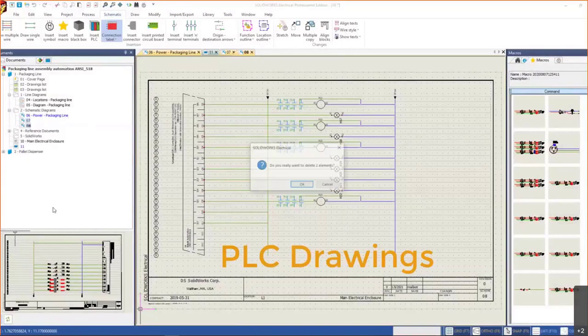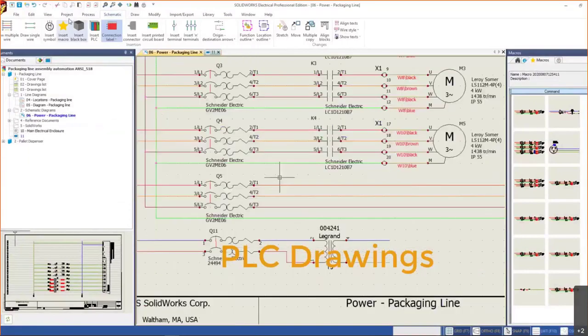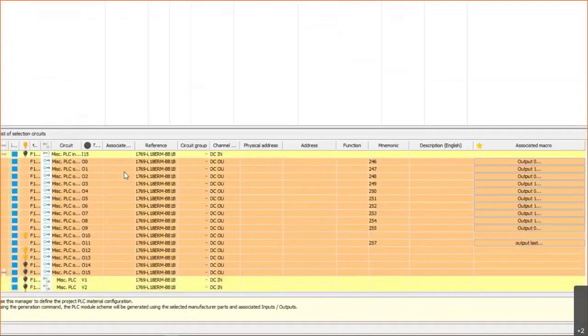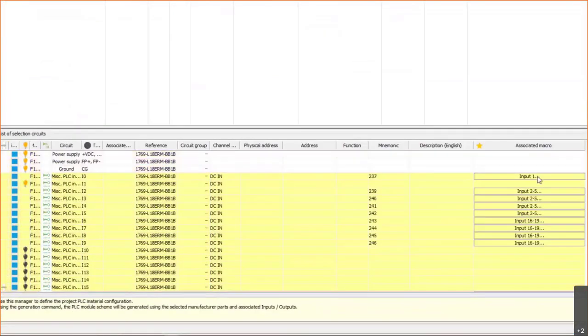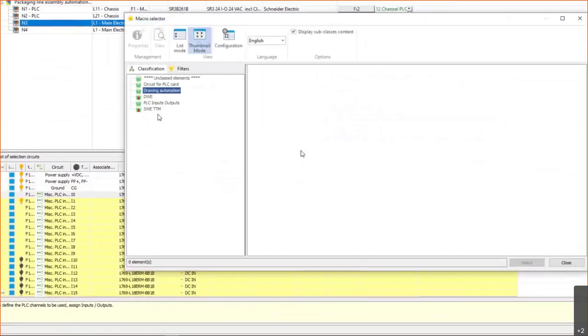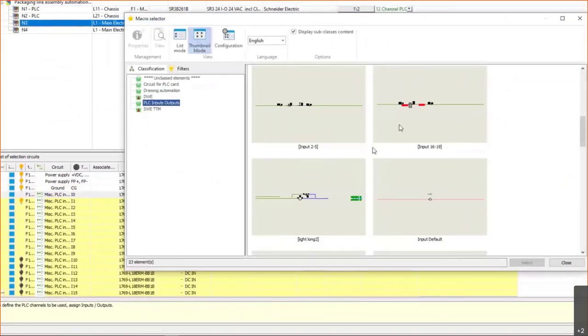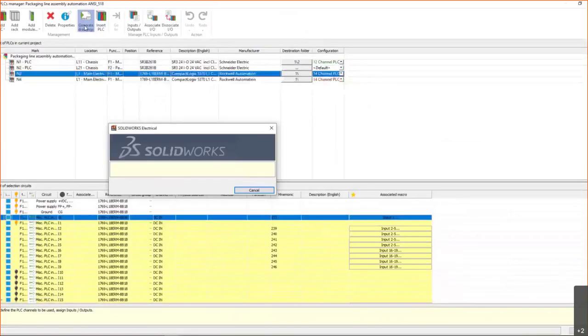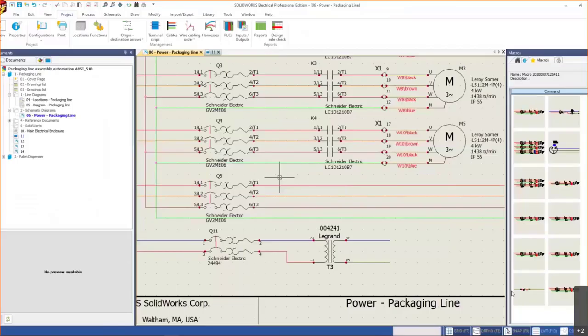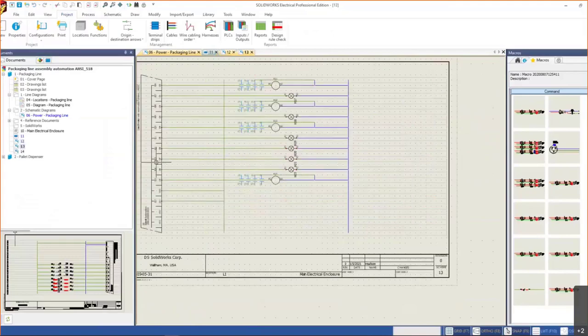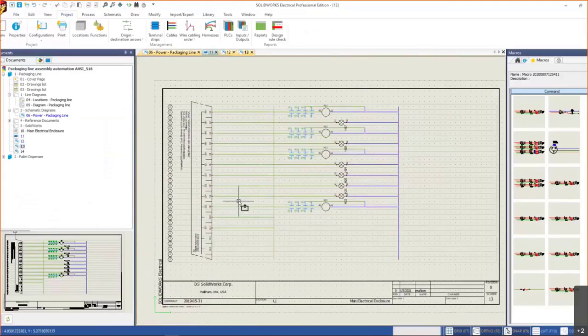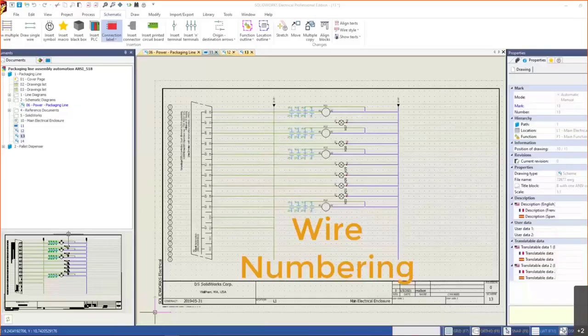PLC drawings here. It's a table view. We've got a table of our PLC. That PLC, it knows my inputs and outputs for that manufacturer part. I can assign a macro, which is a circuit. To each channel. So I can pick an indicator light. Maybe I have an alarm circuits, a relay coil, whatever it is. I hit generate and those configurations are going to know, hey, if it's an input, let's draw the symbol on the right. It's an output on the left and you can set that up.